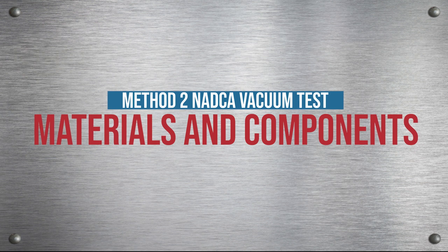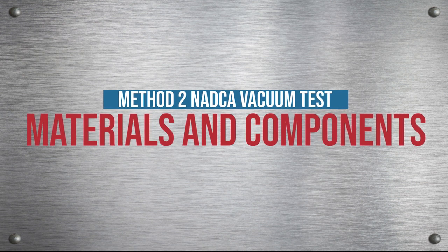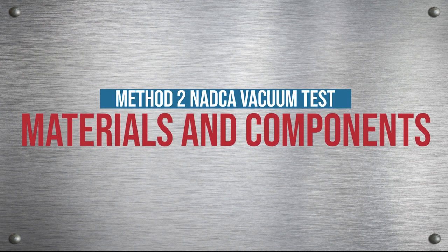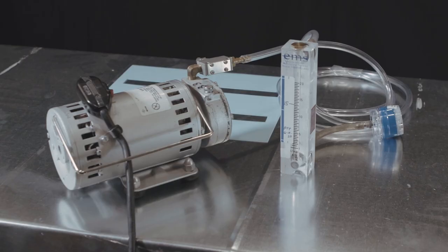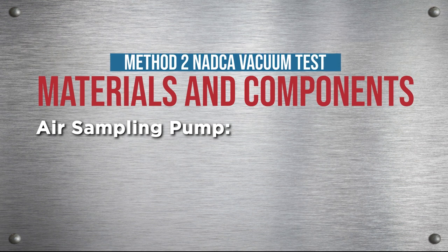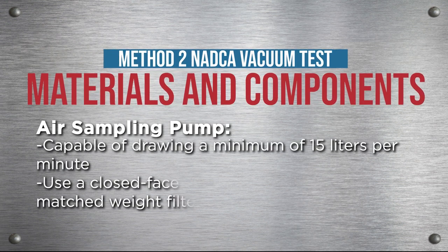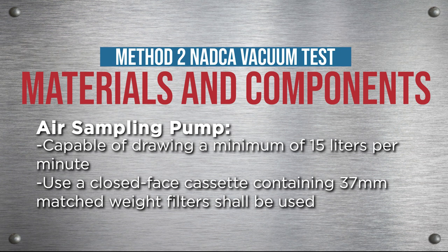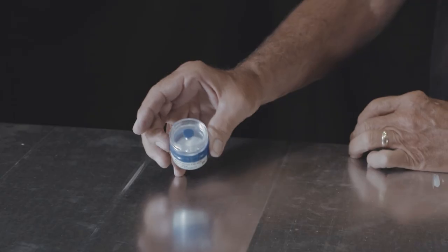The following describes the materials and test components used to perform Method 2 NADCA vacuum test verification. Air sampling pump: an air sampling pump capable of drawing a minimum of 15 liters per minute through a closed face cassette containing 37 millimeter matched weight filters shall be used.